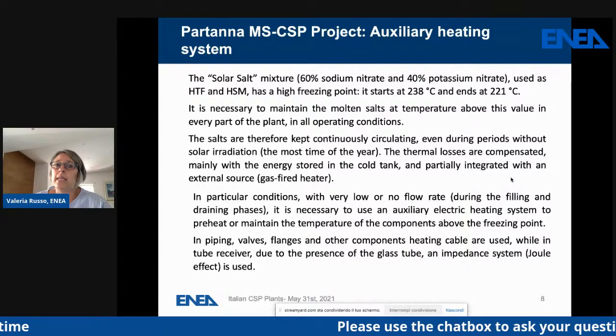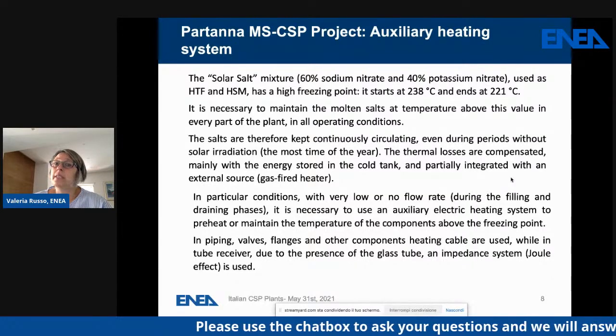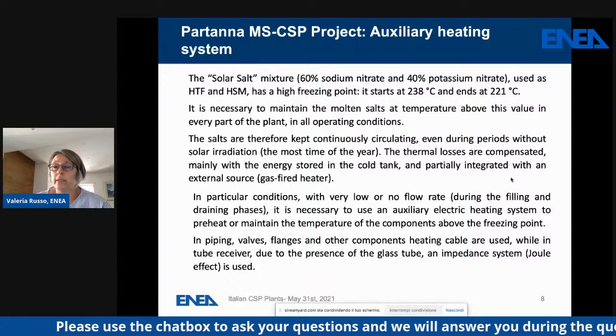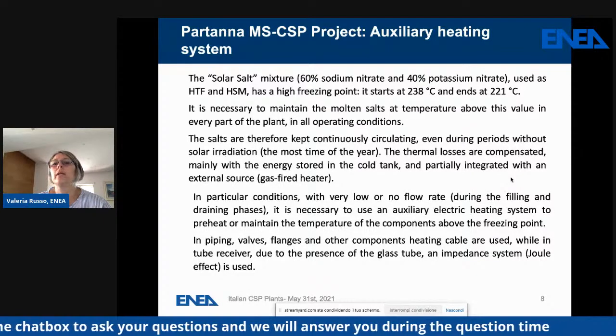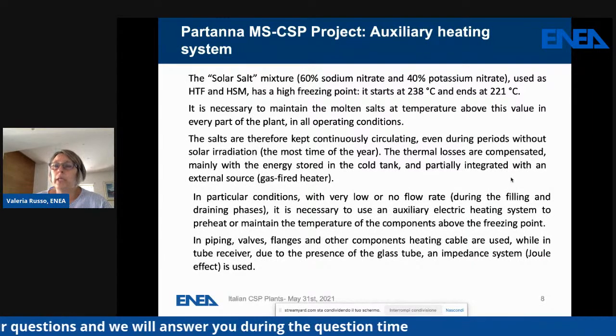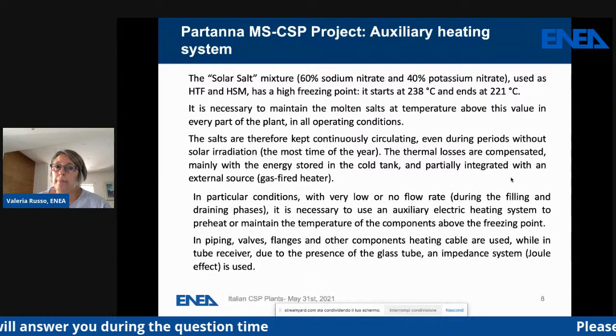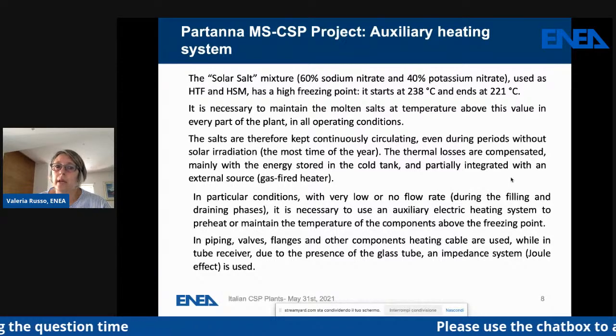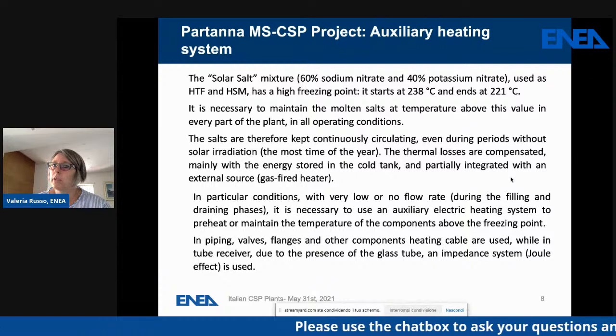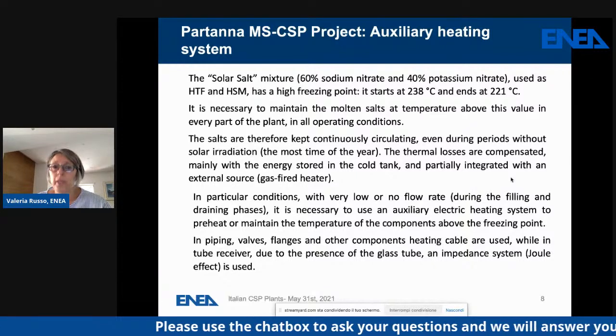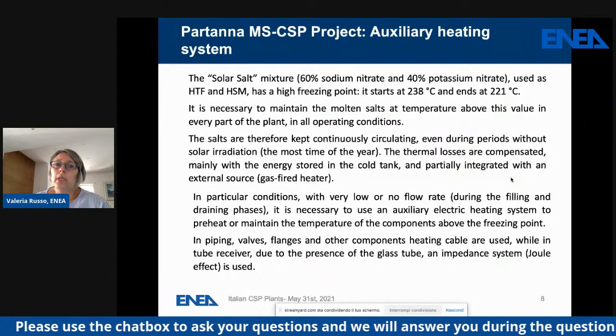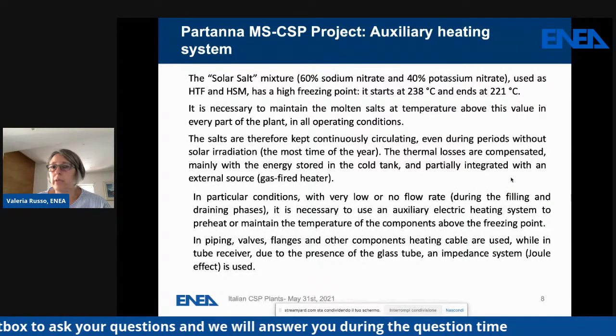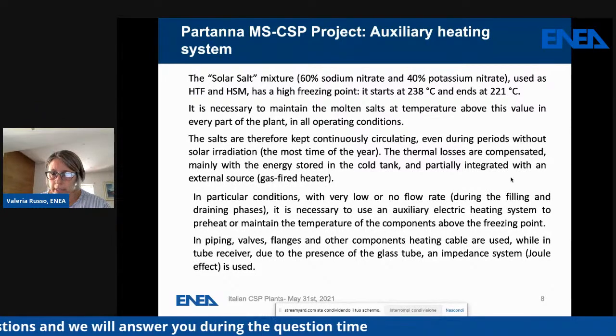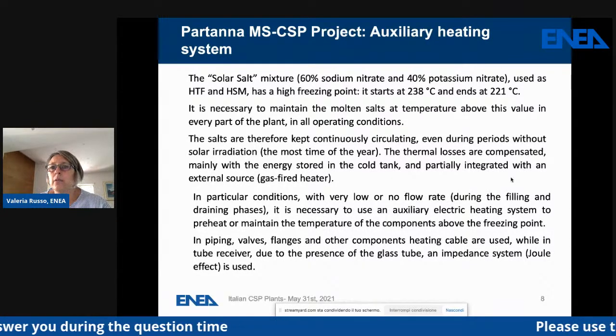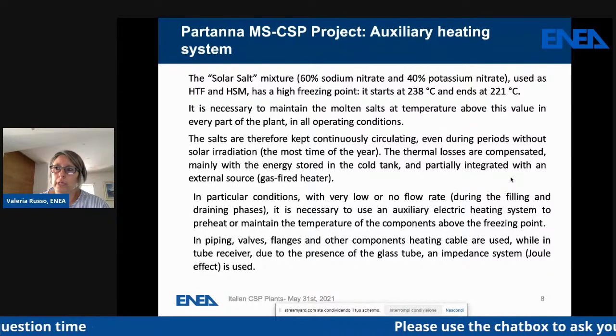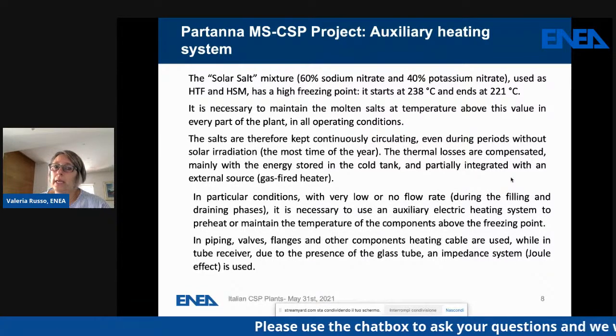This mixture has a high freeze point. In fact, it starts to freeze at 238 degrees centigrade and ends at 221 degrees centigrade. So it is necessary to maintain the temperature of the molten salt in every part of the plant and in all operating conditions above this value. First of all, we have to say that the salt is kept continuously circulating, even during periods without solar irradiation.